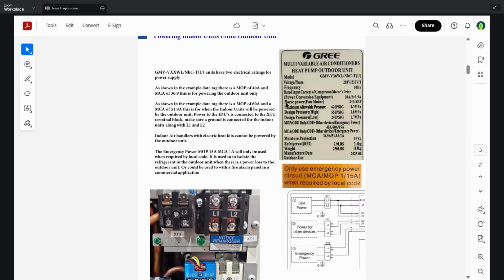So continuing on here to the next page, this is what I was talking about, the capability of the outdoor unit being able to actually power up the indoor units. And there's a lot of information here that you'll need to follow when you want to utilize this XT3 terminal block. This XT3 terminal block is the one that is going to carry the power to the indoor units. And if this is utilized, as we see here on the nameplate, you will have to follow the MOP for utilizing the outdoor terminal block XT3. So that is of 60 amps.